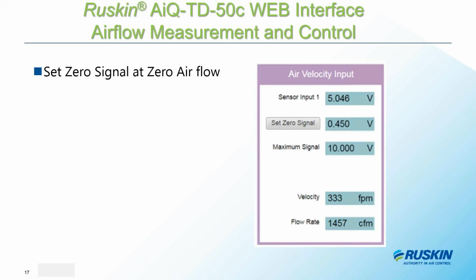So now what we've done by configuring the actuator is we've put all this information into the actuator, and now the actuator can put all of that information out onto the network via a BACnet interface. But this really completes the setup of the actuator. Those are the steps that have to be done to configure the air measurement station.